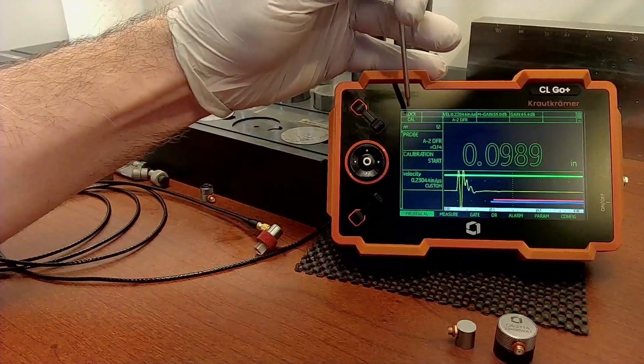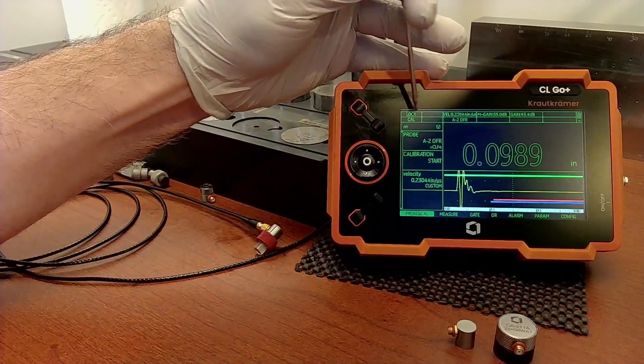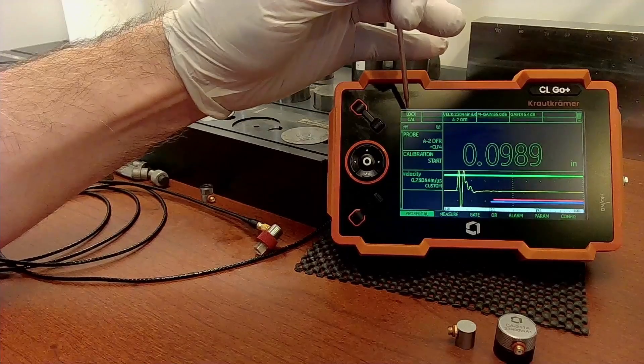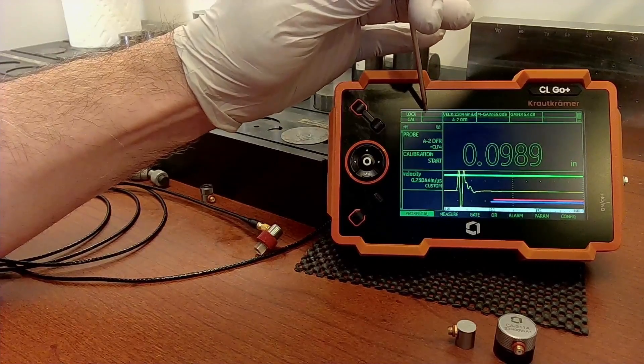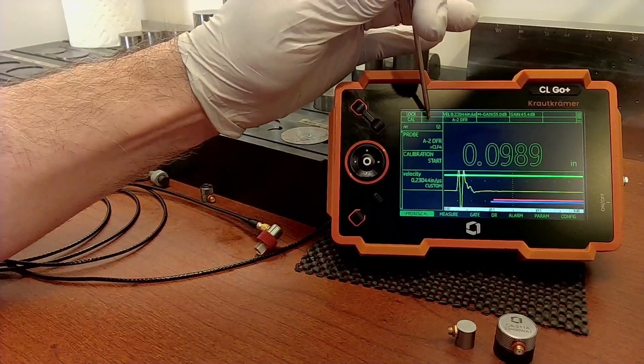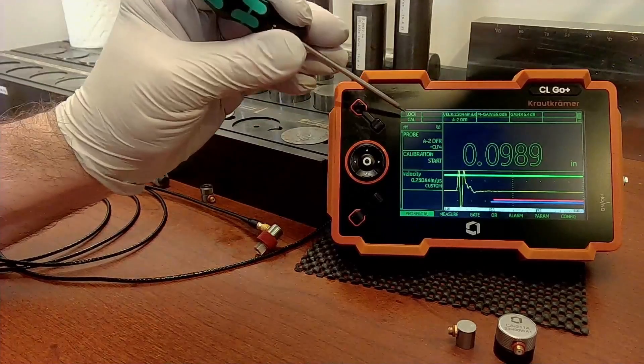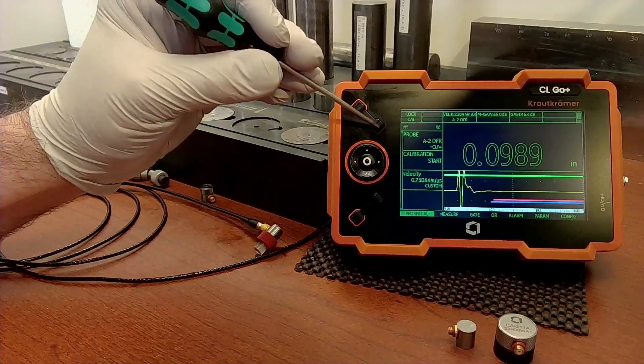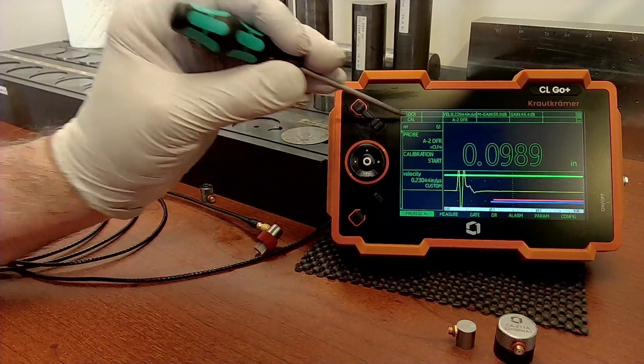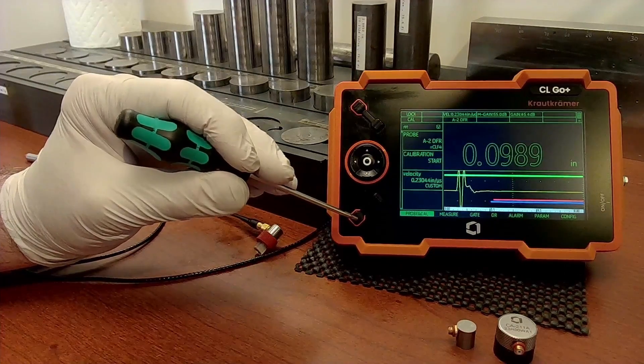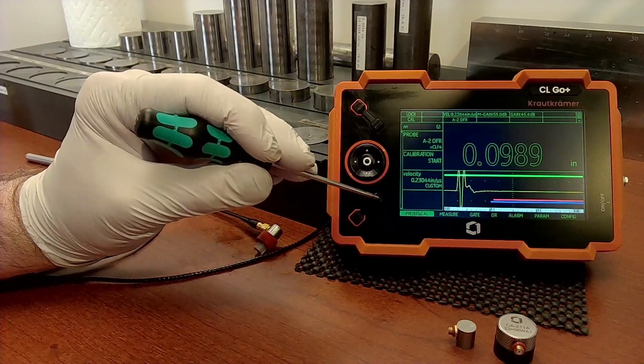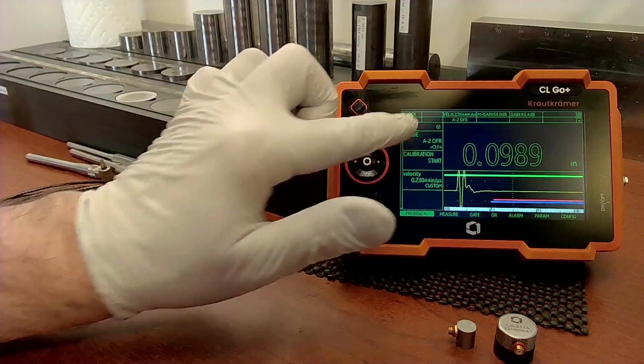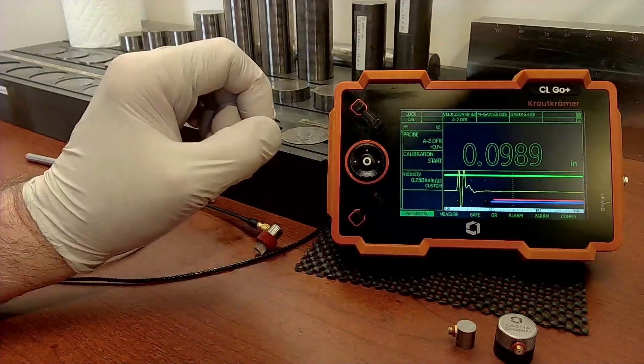One thing to be aware of in the upper left corner of the screen, there are four small boxes. Right now I have one box is lock, this one's blank, this one's cal, this one's blank. So lock is the function performed by this function key. This function key is unassigned at the moment. Down in this corner is the cal and this function key is unassigned at the moment. As we go through different processes on the instrument, you may see those function keys change.